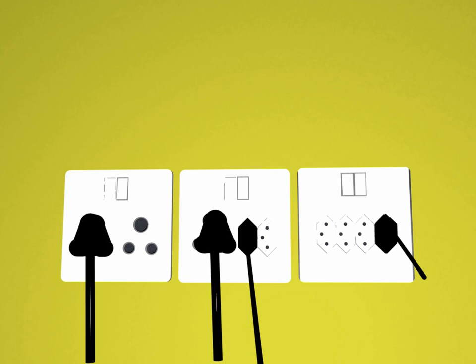IEC 60906-1 plugs and socket outlets are rated 16A, 250V AC and are intended for use on distribution systems having nominal voltages between 200V and 250V AC. IEC 60906-1 defines both three-pin connectors for Class I appliances and two-pin versions for Class II appliances. Additional oval-shaped two-pin connectors for Class 0 appliances defined in the first edition of the standard were never implemented and no longer appear in the current second edition. The IEC 60906-1 plugs are smaller than any other European plug with 16A rating, being only slightly larger than the 2.5A Euro plug and providing much more reliable contact.